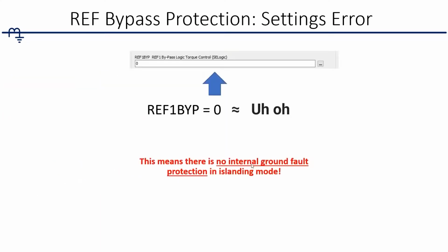It turned off this logic gate here, and the result of this was blocking a trip for an internal ground fault, which for a microgrid situation is already tough enough. That's a pretty big deal. That fault could persist for long periods of time, and it's a pretty major safety issue. So this manifested itself in a way that was a safety concern, in the sense that there was no internal ground fault protection in islanding mode.